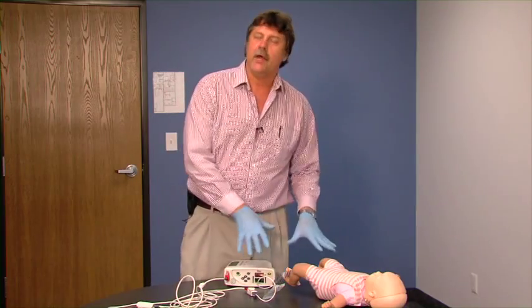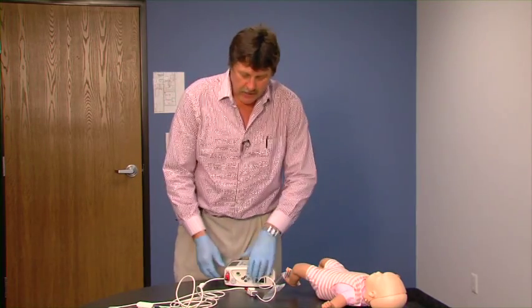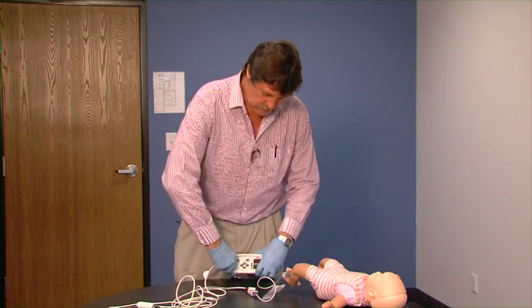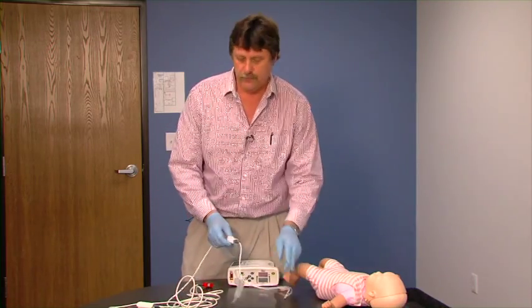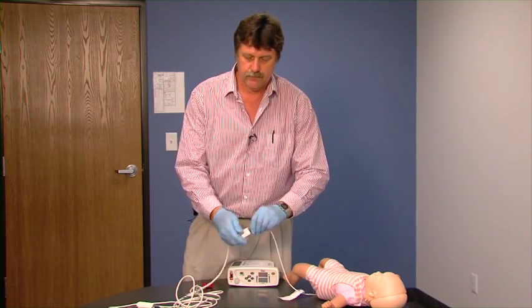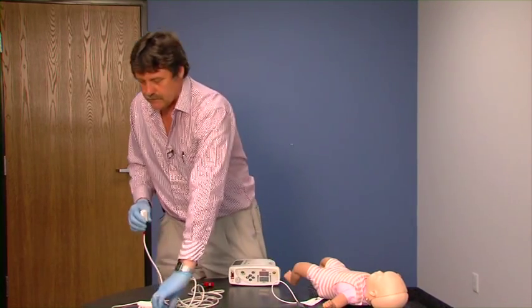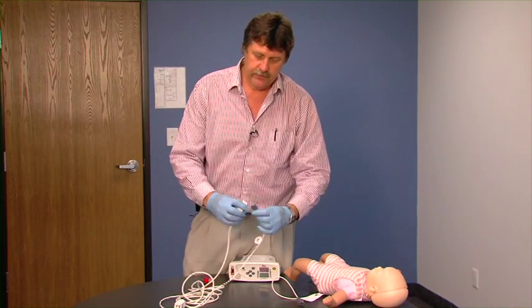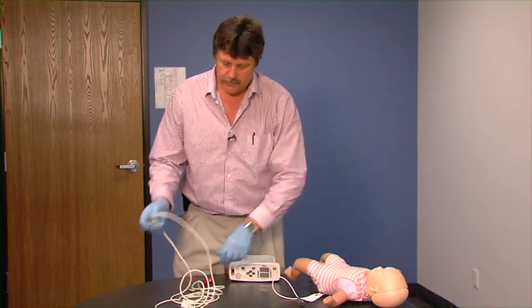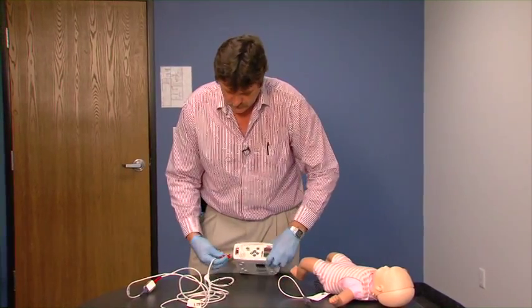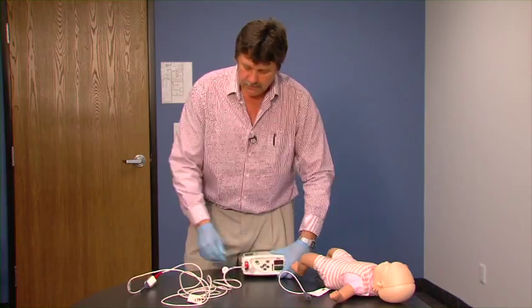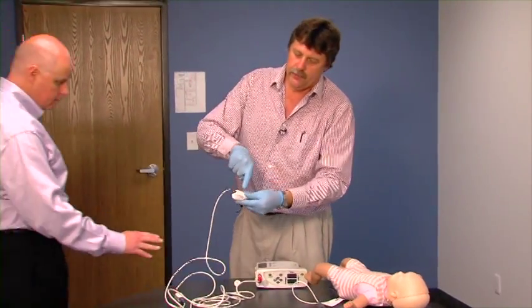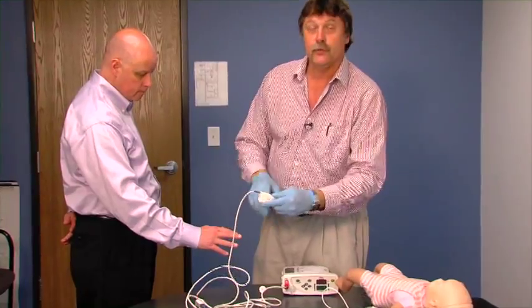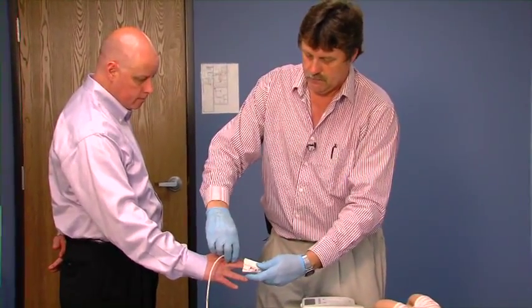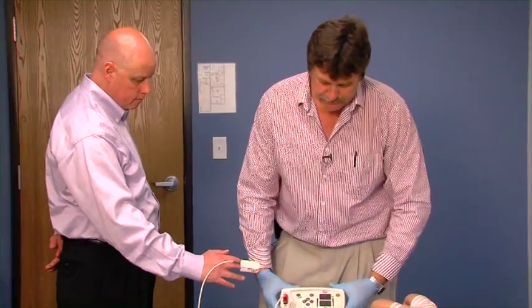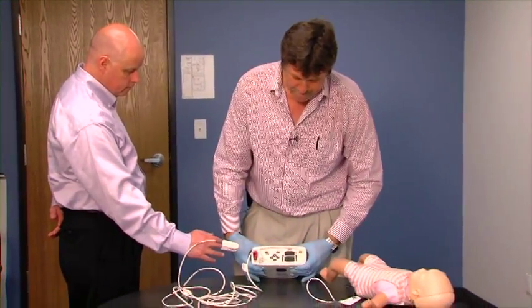Now, this is how we would set it up on an infant. However, if we have an adult, then we use a different probe. We use the finger probe. Take this off and insert the finger probe. Lock it into place. Okay. There is a depiction of the finger on the top of the unit so that you know which side is up. Okay. So we'll put that on our patient and see what our values are.